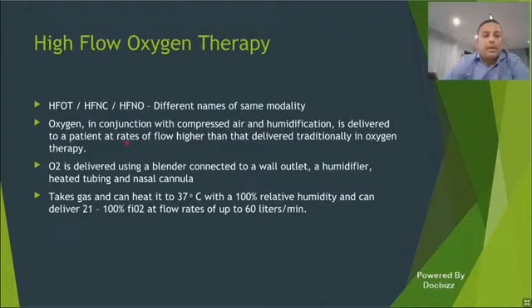Again, what it does is oxygen in conjunction with compressed air and humidification is delivered to the patient at rates which are much higher than traditional oxygen therapy through a simple cannula. You have a blender connected to the wall outlet, you have a humidifier, you have heated tubing, and you have a cannula. Those are all the components of your high flow. It takes the gas, heats it up to 37 degrees, adds 100% relative humidity, and then delivers oxygen at concentrations of 21% to 100% at different flow rates. It can go from 30 liters to 60 liters per minute.